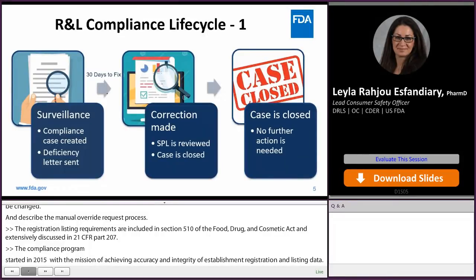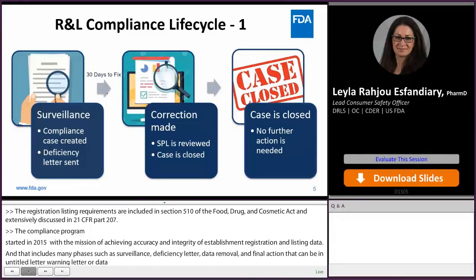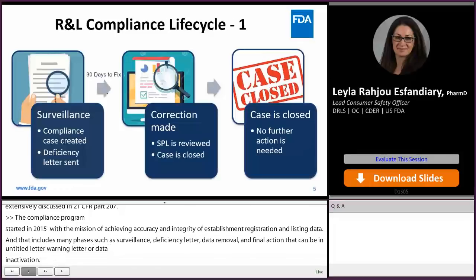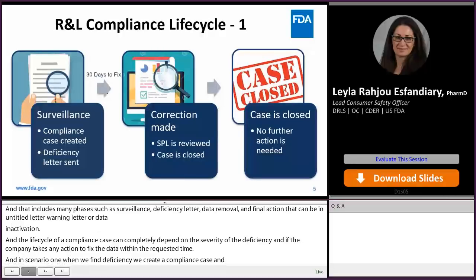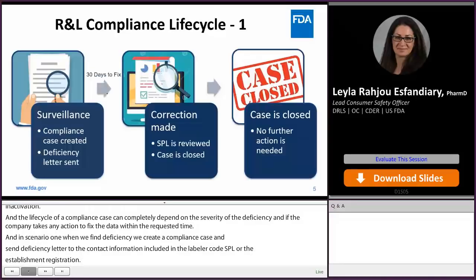The lifecycle of a compliance case depends on the severity of the deficiency and whether the company takes action to fix the data within the requested time. In scenario one, when we find a deficiency, we create a compliance case and send a deficiency letter to the contact information included in the labeler code SPL or the establishment registration. We give firms 30 days to fix the data. If the correction is made, the SPL is reviewed by staff and the case is closed. Once the case is closed, no further action is needed.